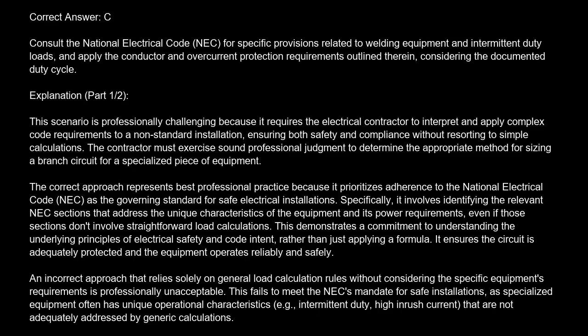documented duty cycle. Explanation. This scenario is professionally challenging because it requires the electrical contractor to interpret and apply complex code requirements to a non-standard installation, ensuring both safety and compliance without resorting to simple calculations. The contractor must exercise sound professional judgment to determine the appropriate method for sizing a branch circuit for a specialized piece of equipment. The correct approach represents best professional practice because it prioritizes adherence to the National Electrical Code, NEC, as the governing standard for safe electrical installations. Specifically, it involves identifying the relevant NEC sections that address the unique characteristics of the equipment and its power requirements, even if those sections don't involve straightforward load calculations.